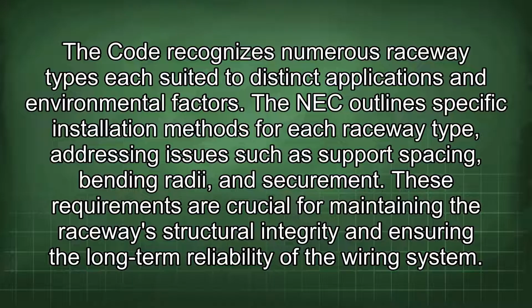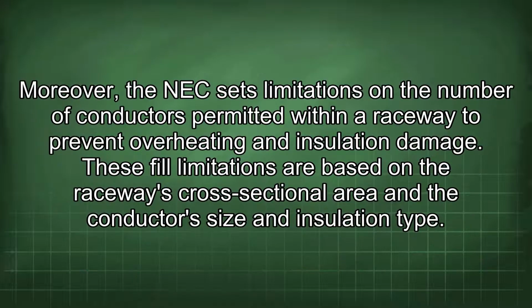The NEC outlines specific installation methods for each raceway type, addressing issues such as support spacing, bending radii, and securement. These requirements are crucial for maintaining the raceway's structural integrity and ensuring the long-term reliability of the wiring system. Moreover, the NEC sets limitations on the number of conductors permitted within a raceway to prevent overheating and insulation damage. These fill limitations are based on the raceway's cross-sectional area and the conductor size and insulation type.